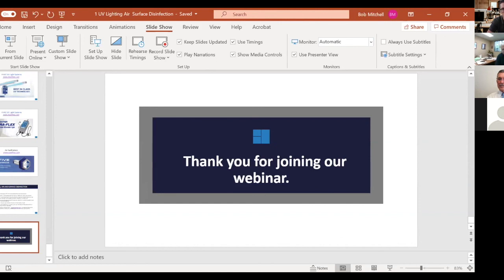have UV lighting. They have 25 air changes per hour. They use HEPA filters. So they're just doubling up, and it deals with, one, if you're laying on the operating table and you're cut open, you want to have no risk of any disease getting in that person.